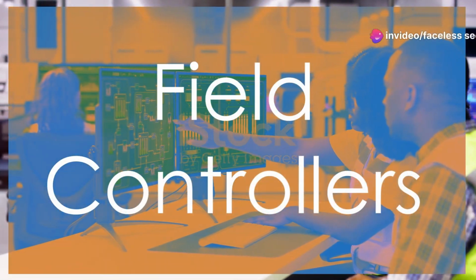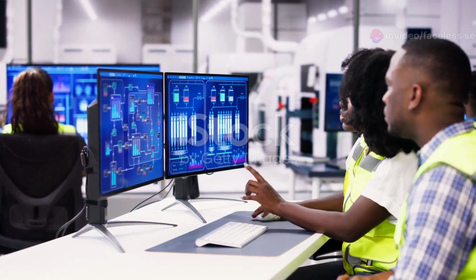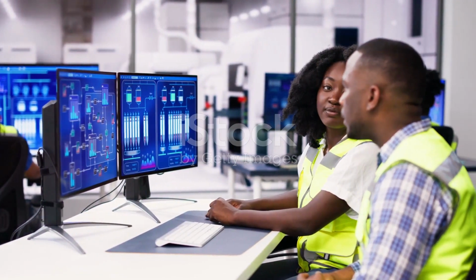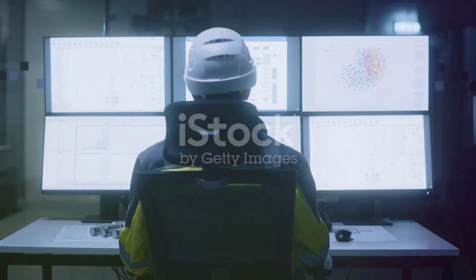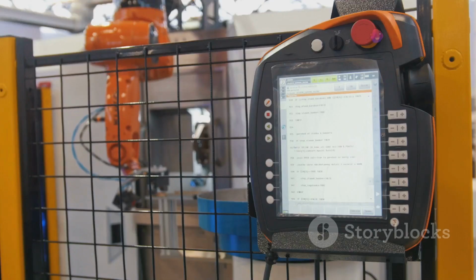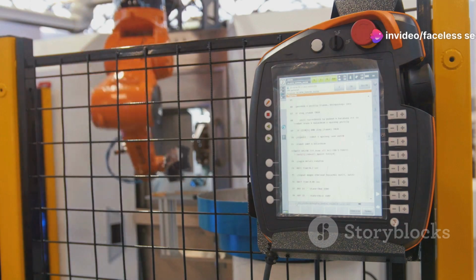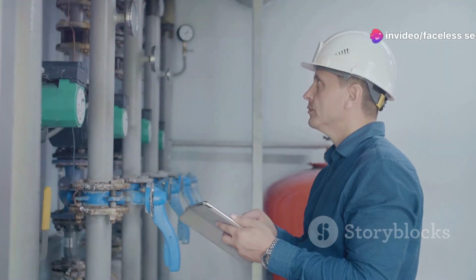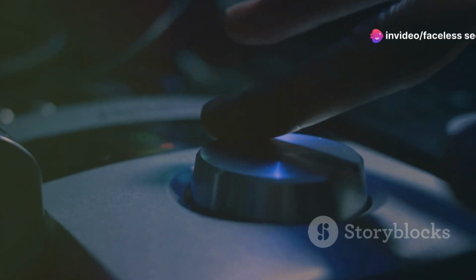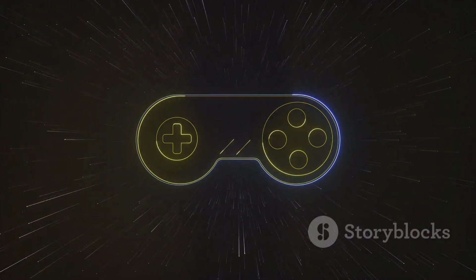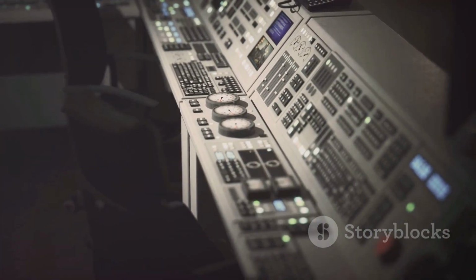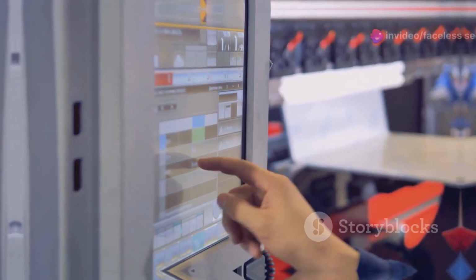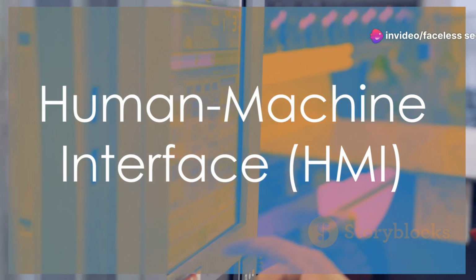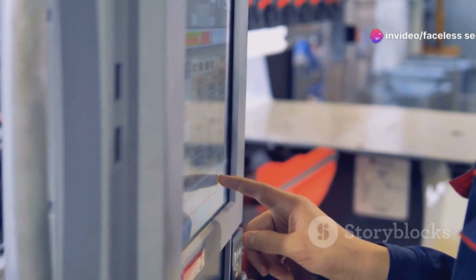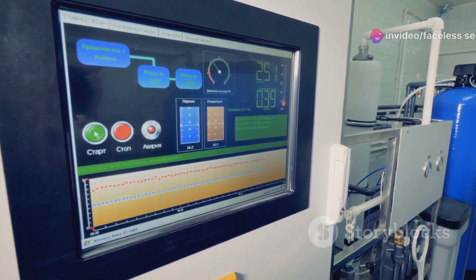Field controllers play a pivotal role in consolidating inputs and outputs, translating operator instructions into actions in the field. These controllers can be programmed or updated remotely, and are designed to operate within a trusted environment. When a command is issued, they respond promptly without authenticating the command source, which can be a security concern if not properly managed.